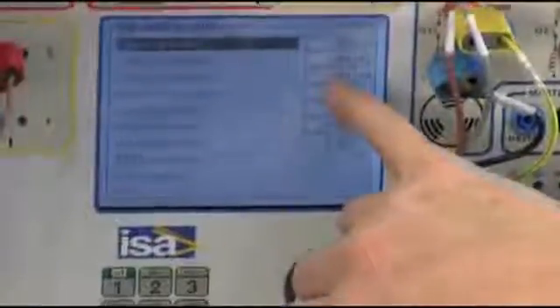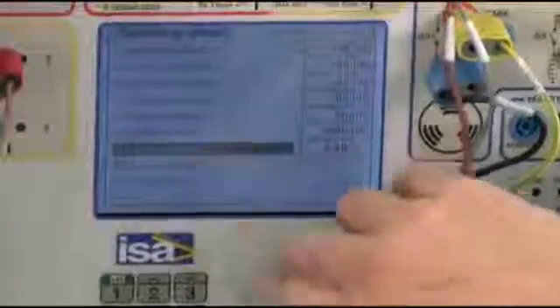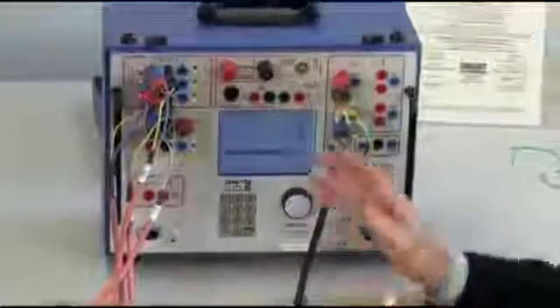So I go here and I see open coil duration, close coil duration. Open to close delay is 300 milliseconds, which corresponds to the standard reclose delay, and this is good. Close to open delay 300 milliseconds, it is good because we can say this is the instance of close on to fault. Pre-trigger, okay, 50 milliseconds, 2 kHz. Recording duration, this value is too short. Why? Because I have 50 milliseconds of pre-fault, then 300, then 300 is 600, 650. I program here 800 milliseconds, that is 0.8 seconds, so that the complete sequence is displayed on the screen.